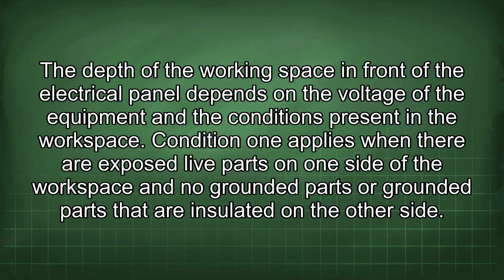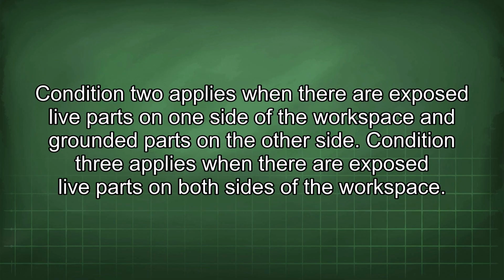Condition 1 applies when there are exposed live parts on one side of the workspace and no grounded parts, or grounded parts that are insulated, on the other side. Condition 2 applies when there are exposed live parts on one side of the workspace and grounded parts on the other side. Condition 3 applies when there are exposed live parts on both sides of the workspace.